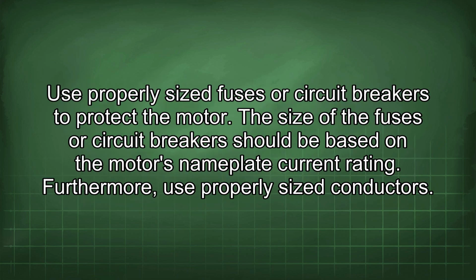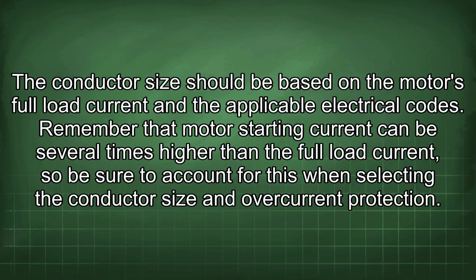Use properly sized fuses or circuit breakers to protect the motor. The size of the fuses or circuit breakers should be based on the motor's nameplate current rating. Furthermore, use properly sized conductors. The conductor size should be based on the motor's full load current and the applicable electrical codes. Remember that motor starting current can be several times higher than the full load current, so be sure to account for this when selecting the conductor size and overcurrent protection.